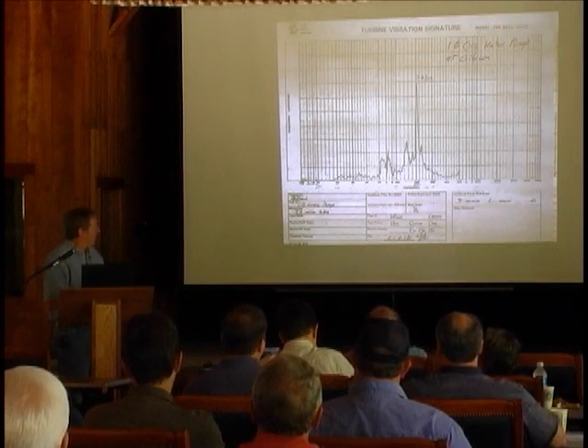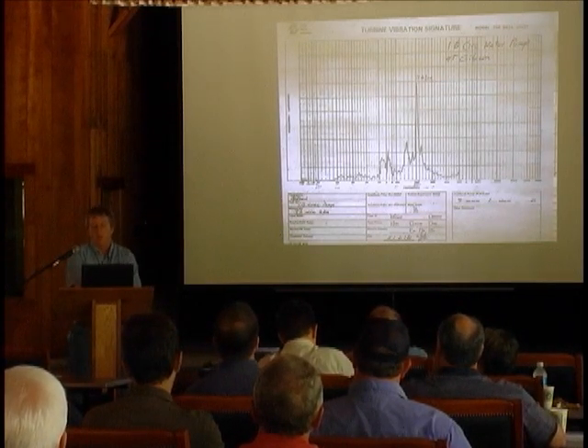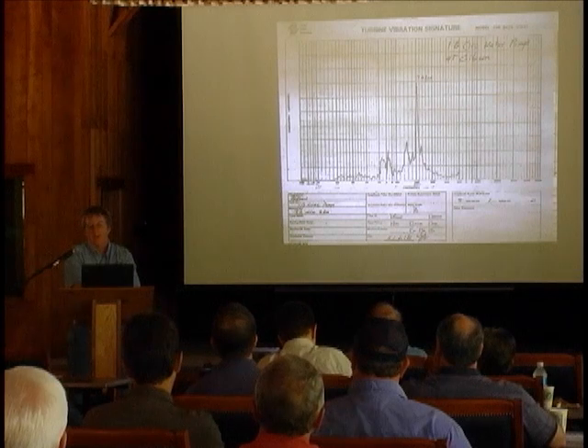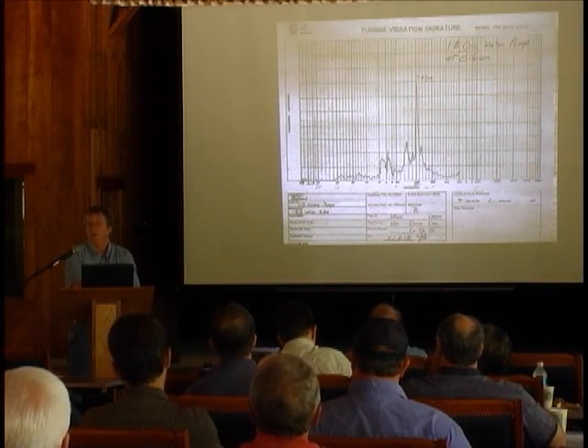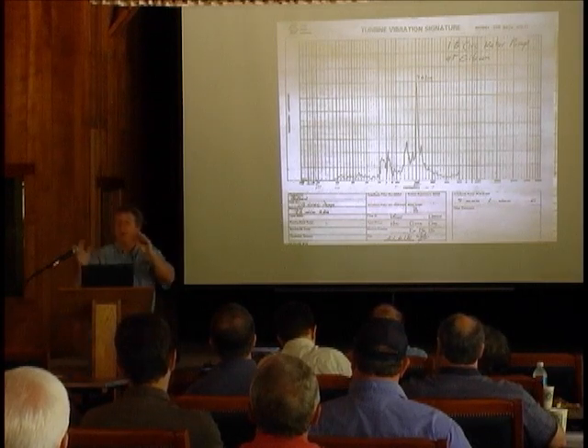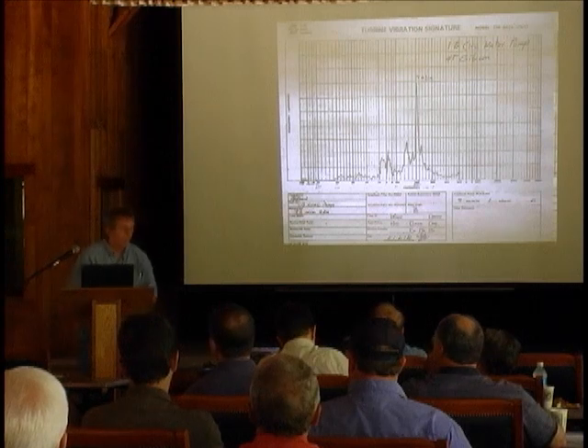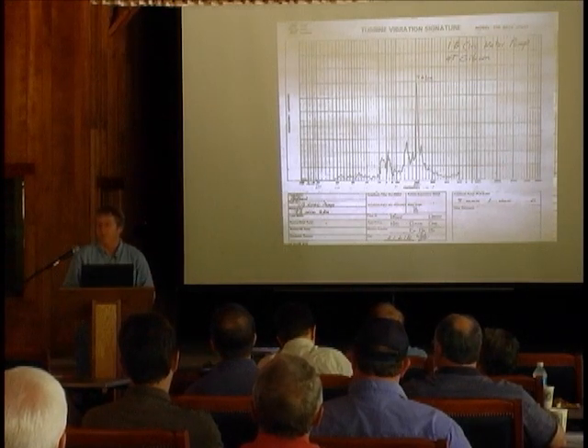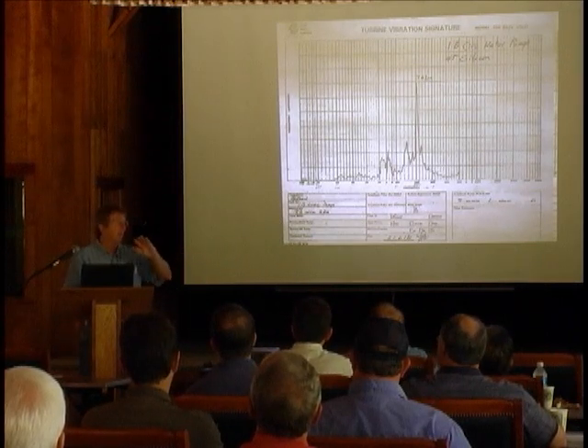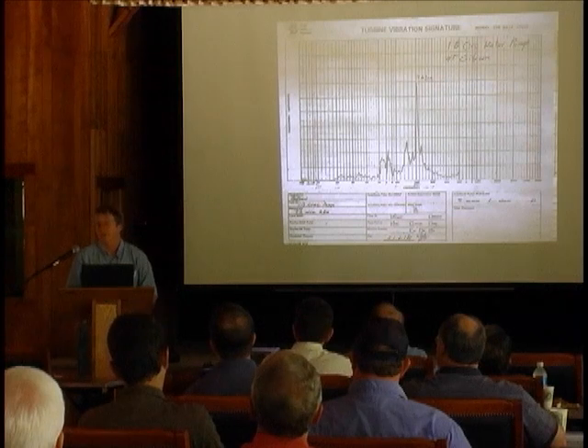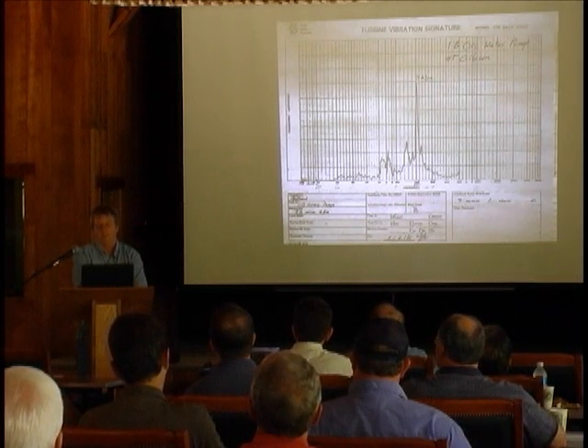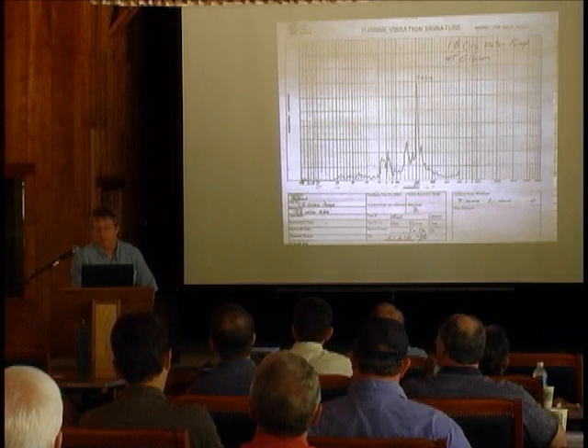So this thing was supposed to be operating against 30 feet of head. I measured it, and it was only operating against 7 feet of head instead of 30 feet. So I got the pump head curve, and the pump head curve didn't even go that far. It was supposed to pump 156,000 gallons a minute at 30 feet of head, and at 7 feet it was on past 210,000 gallons a minute. It was just clear off the chart. So I wonder what's going on here? How is this happening?